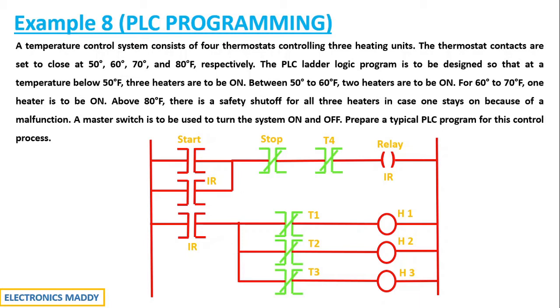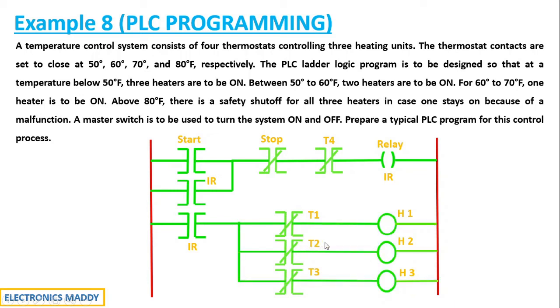Let me start the process by turning on the system. If you press the start push button, current starts flowing through this path and the entire rung gets energized. Consequently, the internal relay (IR) will get energized. According to the concept of latching, the same IR address is used here as well, so since this goes high, this will also go high. Since all of them are turned on, current flows through each branch and all the heating units will be turned on. This is for temperature below 50°F — the first condition is satisfied.